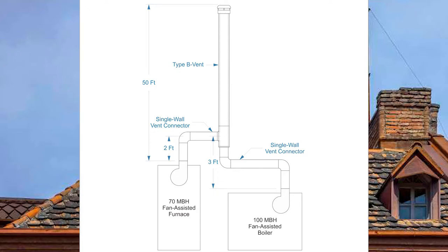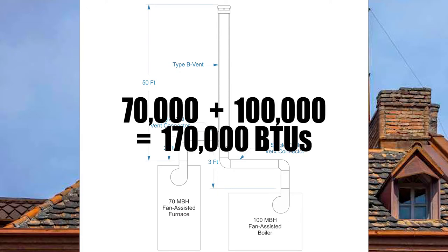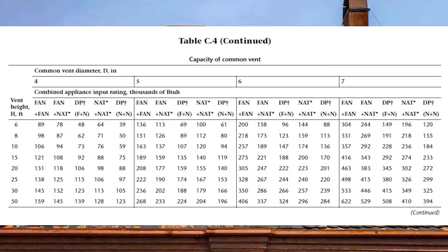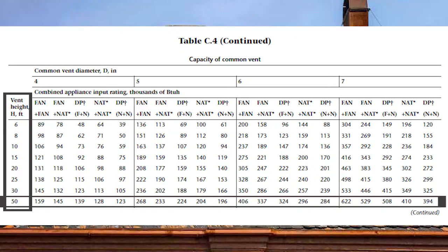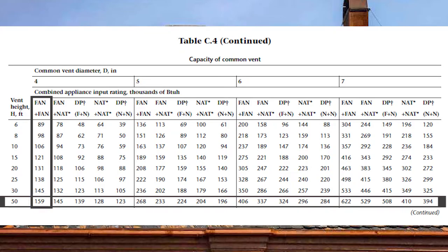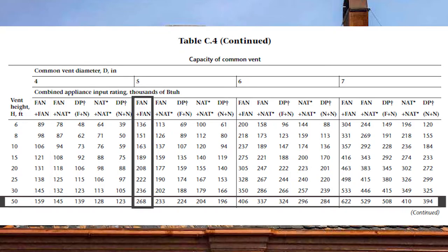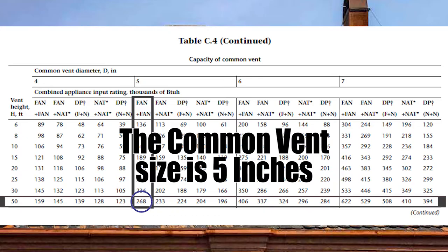Before sizing the common vent I need to combine the BTU load: 70,000 plus 100,000 equals a total BTU load of 170,000 BTUs. Turning to page 206 and coming down to a vent height of 50 feet, I'm looking for fan plus fan since I only have fan assisted appliances. The four-inch common vent is 159,000 BTUs — not quite enough. So I go to the five-inch common vent, which is good to 268,000 BTUs. I have a five-inch common vent.